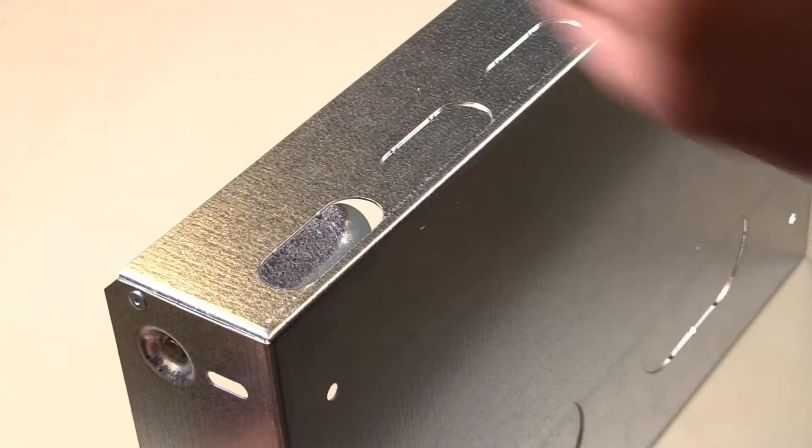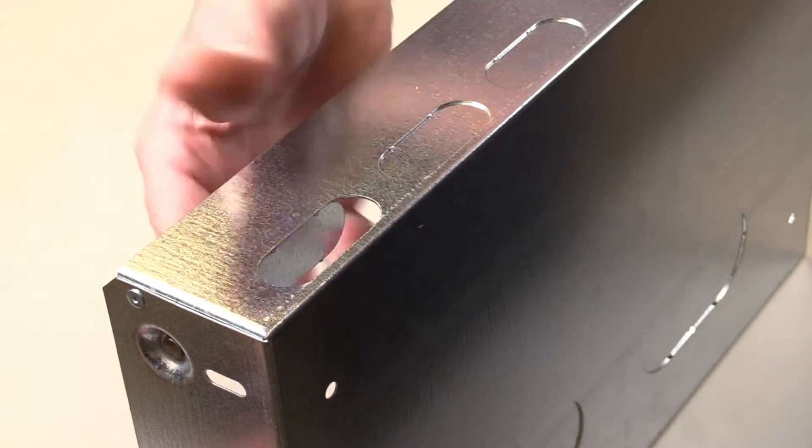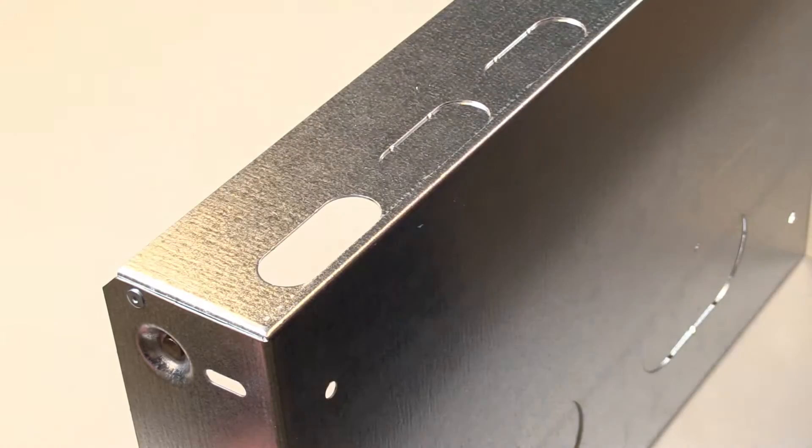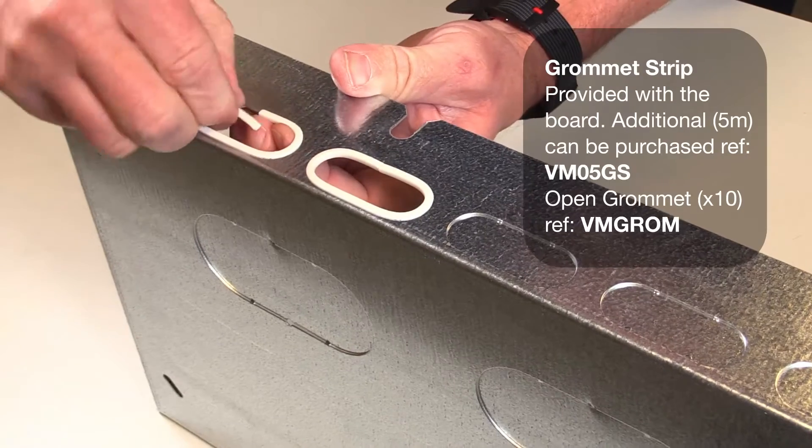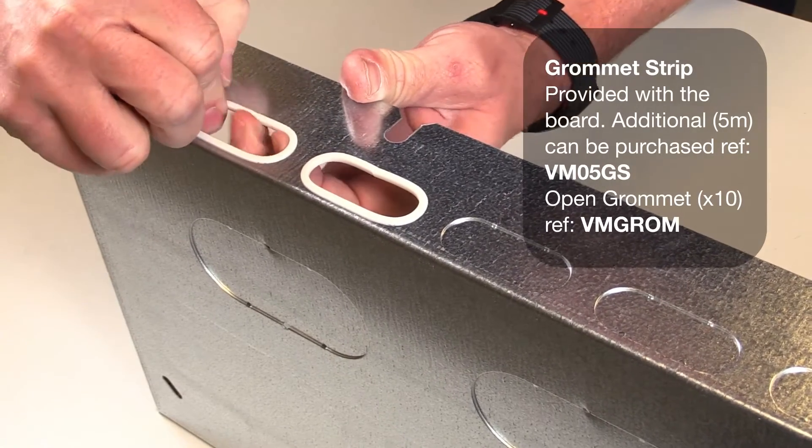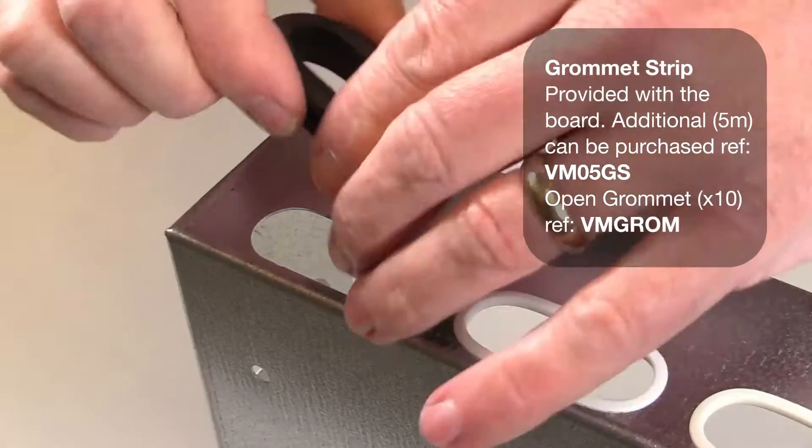There are knockouts on the top, bottom, sides, and rear of the enclosure. This facilitates cable entry for many different installations. The cable entries at the top and the bottom of the back box leave you a knockout which can be protected by either using the included grommet strip or a 38 millimeter open grommet.